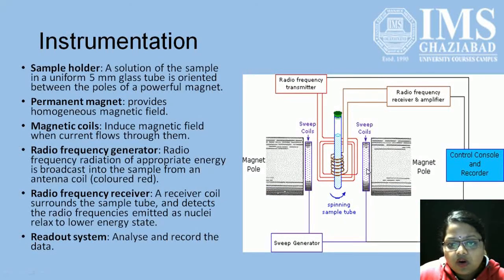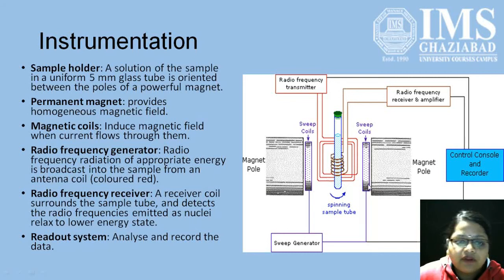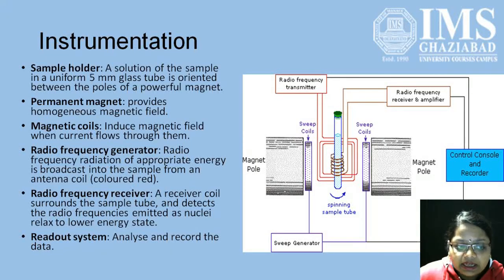This is the instrumentation of a simple NMR spectroscopy. First, we have the sample holder, a solution of sample in a uniform 5mm glass tube oriented between the poles of powerful magnets. We have permanent magnets to provide the homogeneous magnetic field and magnetic coils to induce magnetic field when current flows through them. We have the radio frequency generator. Radio frequency radiation of appropriate energy is broadcast into the sample with the help of antenna coils. We have the radio frequency receiver. The receiver coil surrounds the sample tube and detects the radio frequencies emitted as the nuclei relax to the lower energy state. When it flips from the higher energy state to the lower energy state, it releases a certain amount of radio frequency energy, which is detected by the detector systems. We have a proper readout system for analyzing and recording our data.